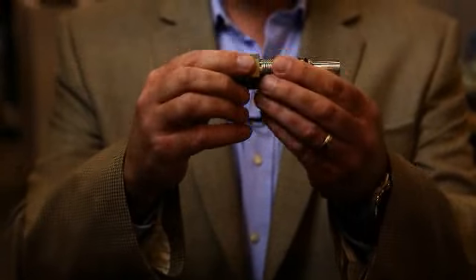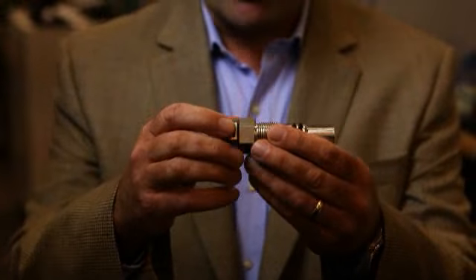Okay, so now we've discussed the capital costs that the meter can afford you. We've also just discussed the operational costs. Now let's talk about how we can service this meter in the event that there is an upset in the field. If there's an upset in the field, the most likely instance will be a transducer problem. Now, transducers can be replaced in the field in the unlikely event something goes wrong without any downtime in the process. So let me just demonstrate to you how the transducer is actually constructed.